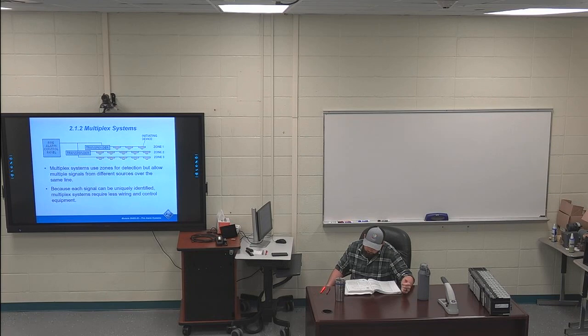So, page 7. Figure 1 shows a typical hardwired system, which is split into zones. But at the bottom, you can see Figure 2, which is a typical multiplex system, which is also split into zones, but they go out by transponders. They can all be connected to a single line, whereas in the hardwired system you have 3 separate lines going out for zones 1, 2, and 3. In the multiplex system, 1 line goes out, and you can split up your zones based on that.